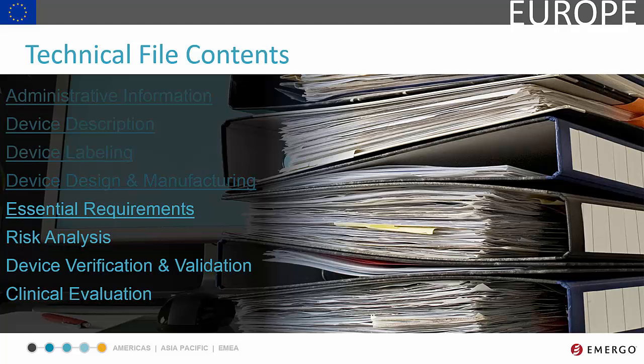The essential requirements are the cornerstone of the entire technical file. They're located within Annex 1 of the Medical Device Directive and are the basic parameters your product must meet. Risk analysis demonstrates a formal analysis was conducted in accordance with ISO 14971, the accepted risk management standard for medical devices. This analysis identifies potential hazards and failure modes of devices and assesses the associated risks.